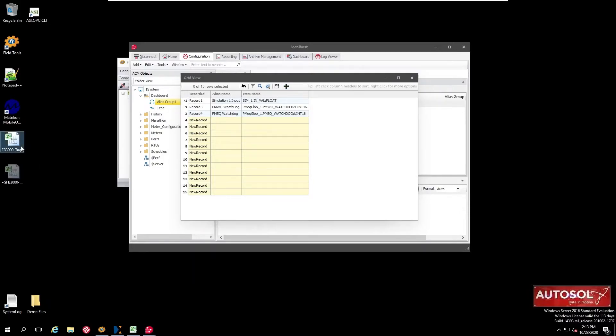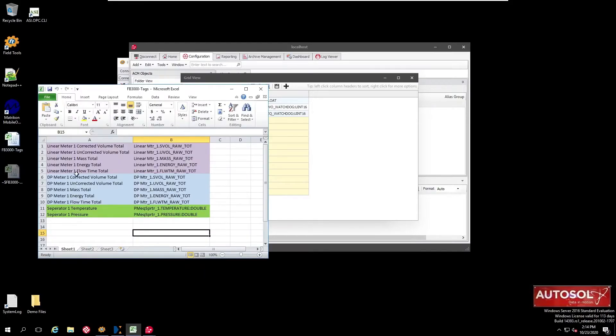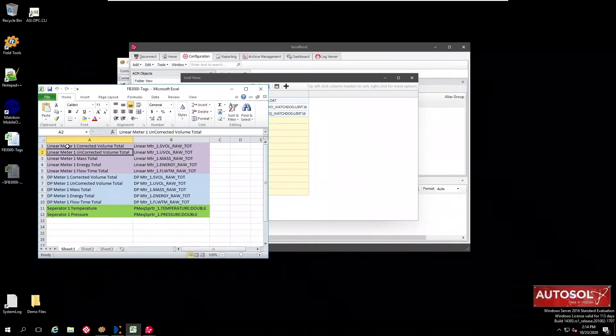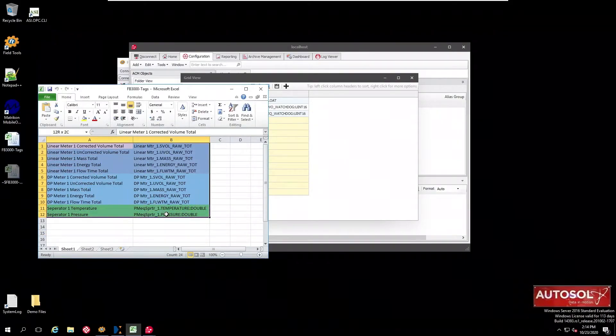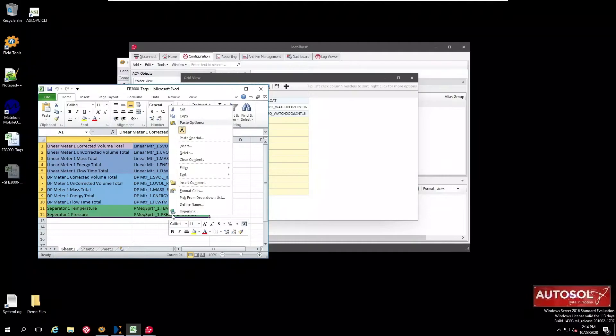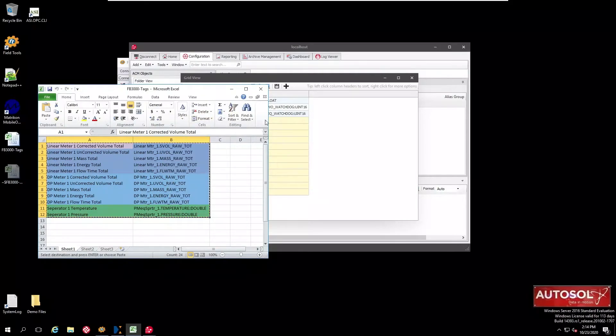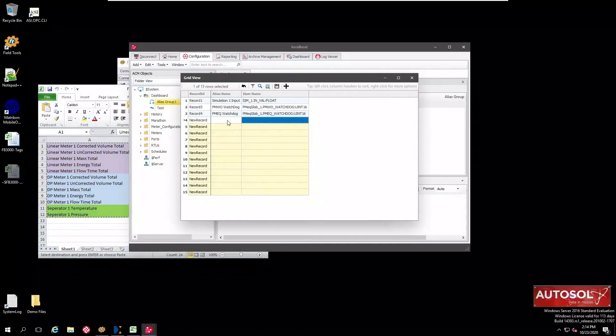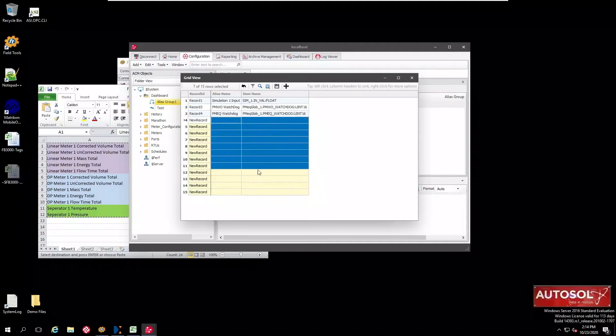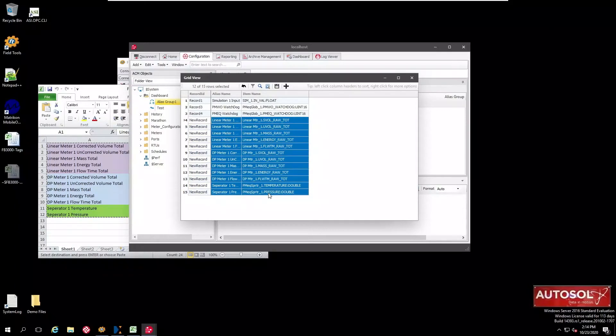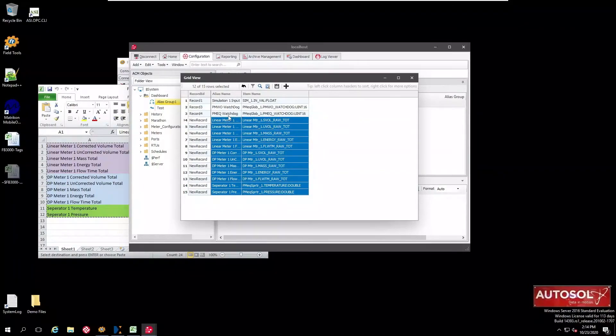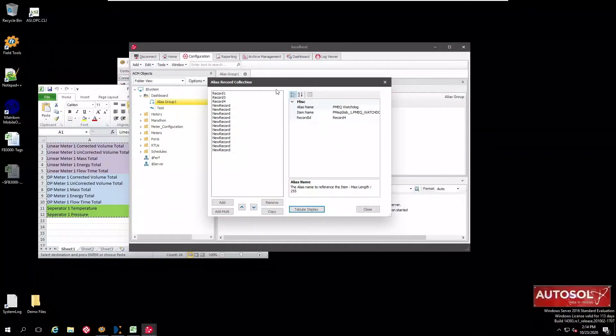Then go to the spreadsheet we created earlier. Select the description and also the tag name. Copy them and then go to ACM configuration. It's important to highlight the fields then press control V to paste those in. You will then need to save your configuration by using the floppy disk icon at the top.